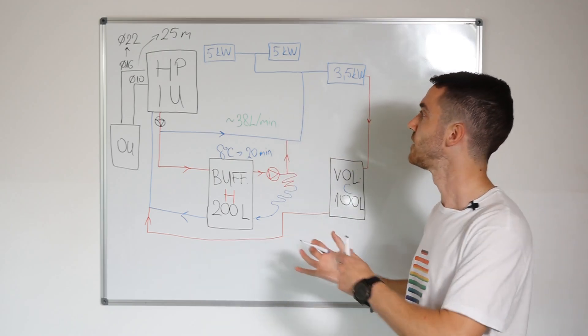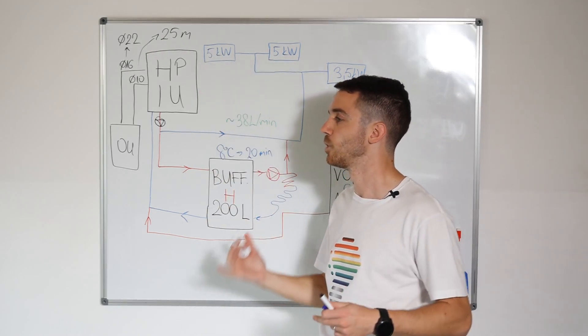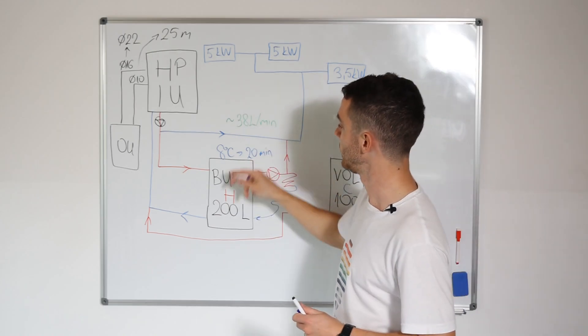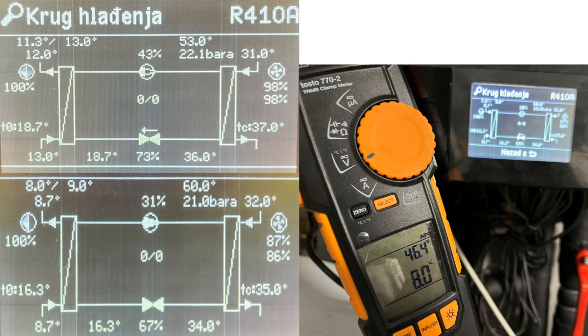So when you put everything on paper, this heat pump, which is 15 or 16 kilowatt, could easily cool this water. And the expansion valve was not full open. Compressor was not on full load. So it was modulating. Customer said that never, never saw this modulation. And we had return around 13 degrees, so delta T 5. Return was 13 degrees. Delta T 5. So everything was clear.